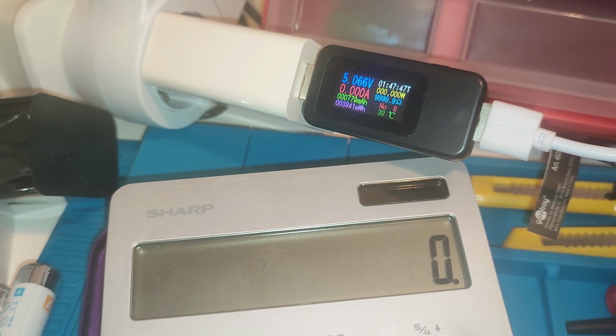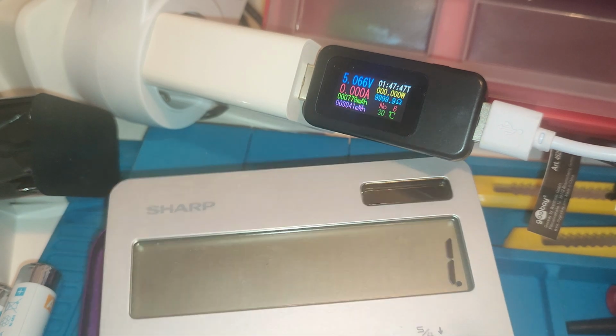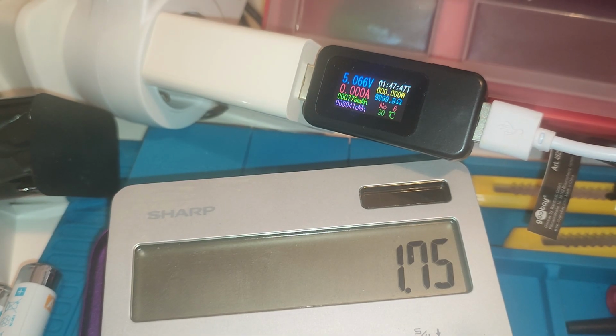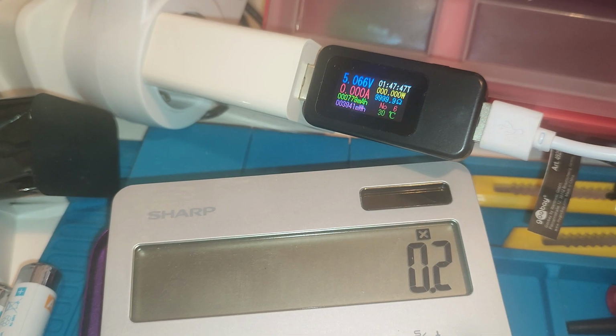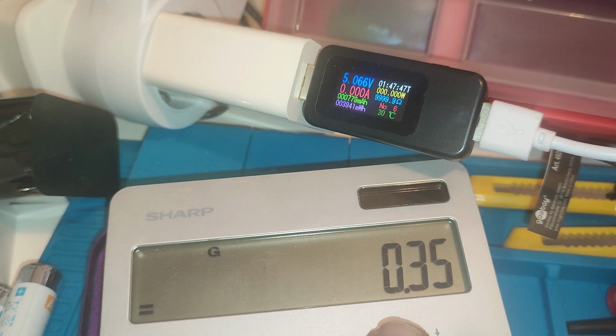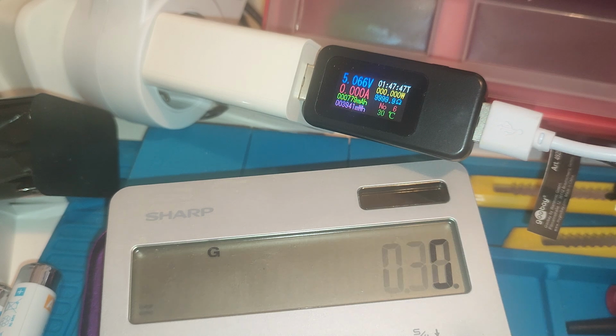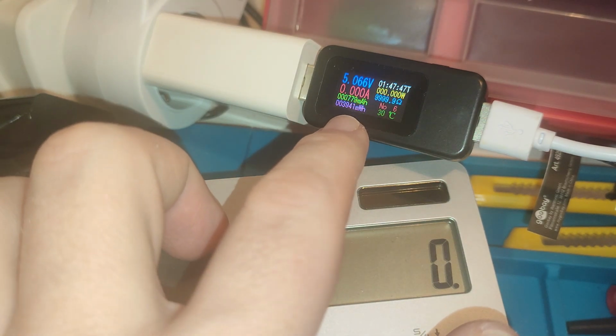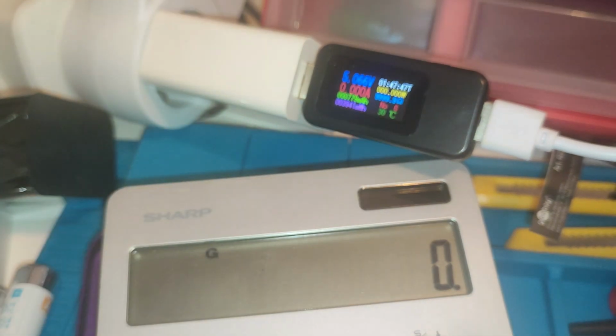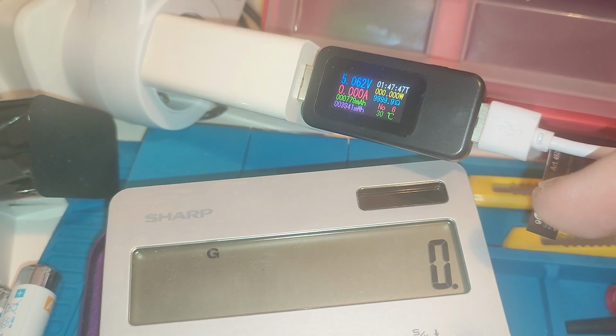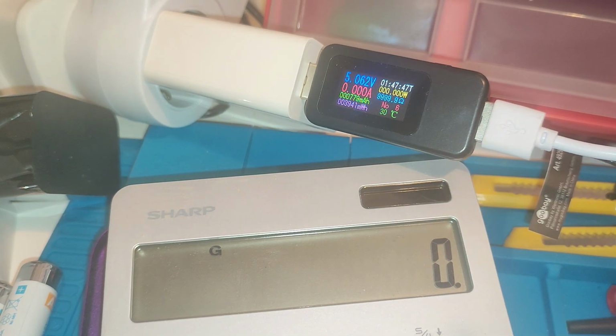Attempting a voiceover instead, since there were some issues with the microphone. Let's try to calculate the battery capacity by subtracting the amount of power used by the display in the unit. So we have about 1.75 hours or so of runtime on the charger. We multiply it by the 200 milliamps of current drawn, so that's about 350 milliamp hours that have been used during the charge cycle by the display, out of the total 775 or so milliamp hours in total.